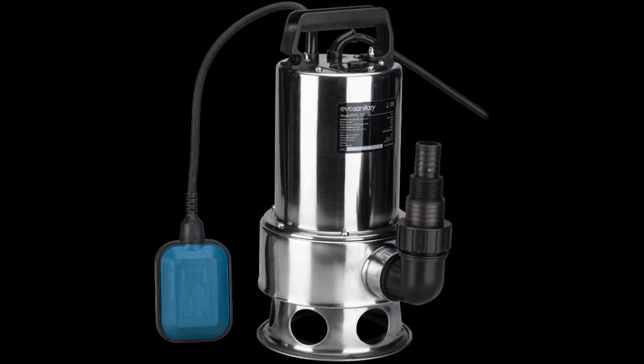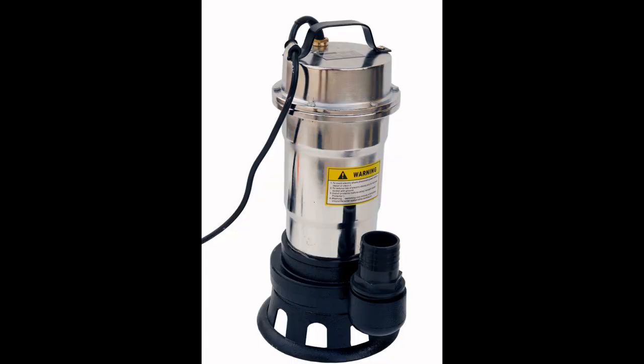The pump can no longer generate pressure because all the power is practically used to raise the water column to that height. It is not recommended to purchase a water pump with a very high discharge height. If a water pump with a high head is used, where there is a low head, the water flow will be too high and the engine will be overloaded. In the case of long-term operation, the engine temperature will increase and cause rapid wear of the engine parts.